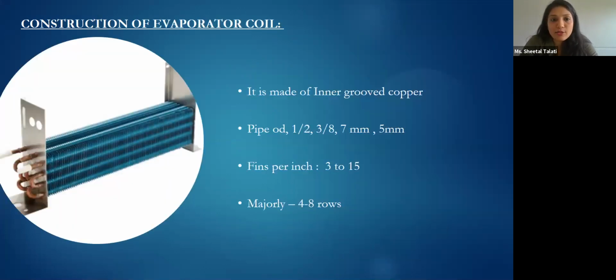Moving on to construction of the evaporator coil. The evaporator coil is also inner grooved pipe. Inner grooved means there is grooving inside the pipe, which helps in better heat transfer. The pipe OD used in evaporator coils is 1/2, 3/8, 7 mm, and 5 mm. And the fins per inch is lesser than the condenser, so it ranges from 3 FPI to 15 FPI, and majorly these coils are found in 4 rows to 8 rows.